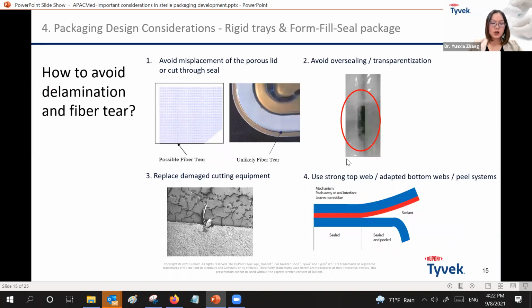So actually, in case of any type of package configuration, good peelability without fiber tear or delamination is required per the usability requirement in ISO 11607. Fiber tear or delamination could generate lots of particles, and microorganisms on the surface of the package may fall onto the product together with the particles, and therefore contaminate the product. So it is very important to avoid the delamination and fiber tear of any type of packaging.